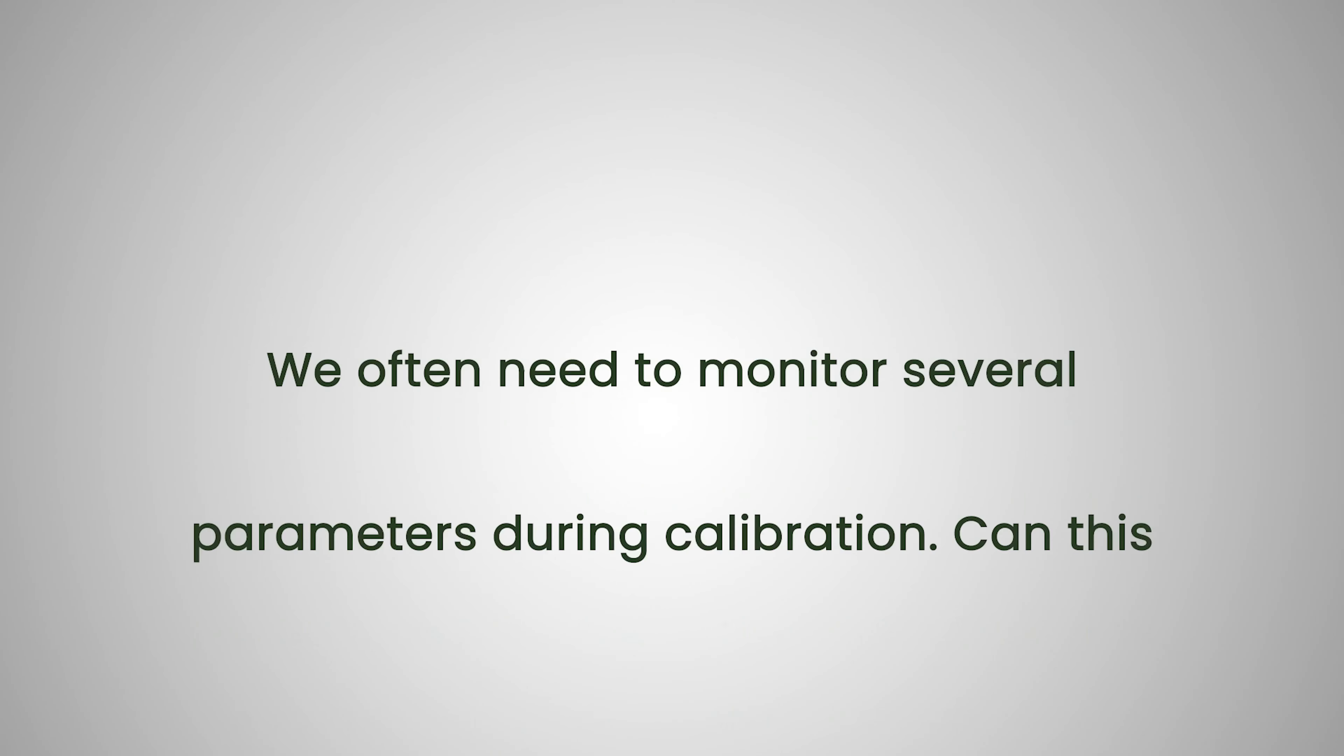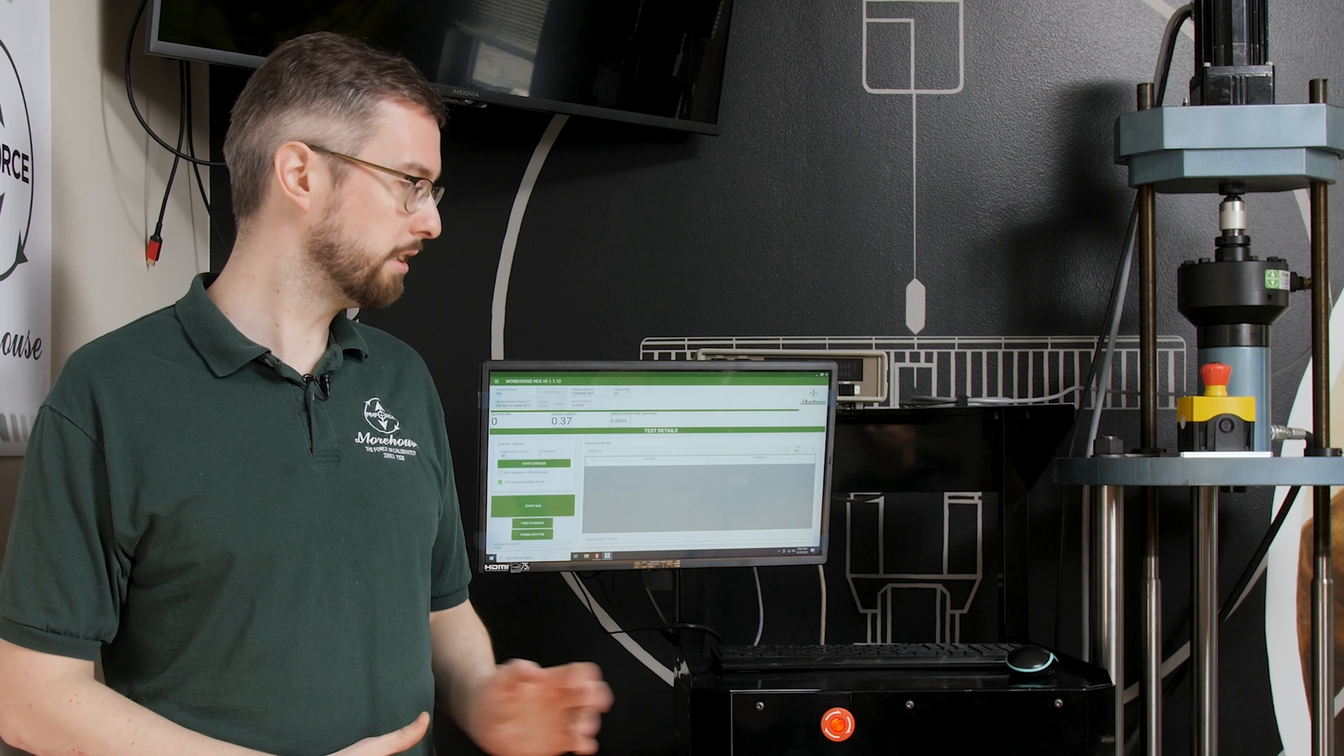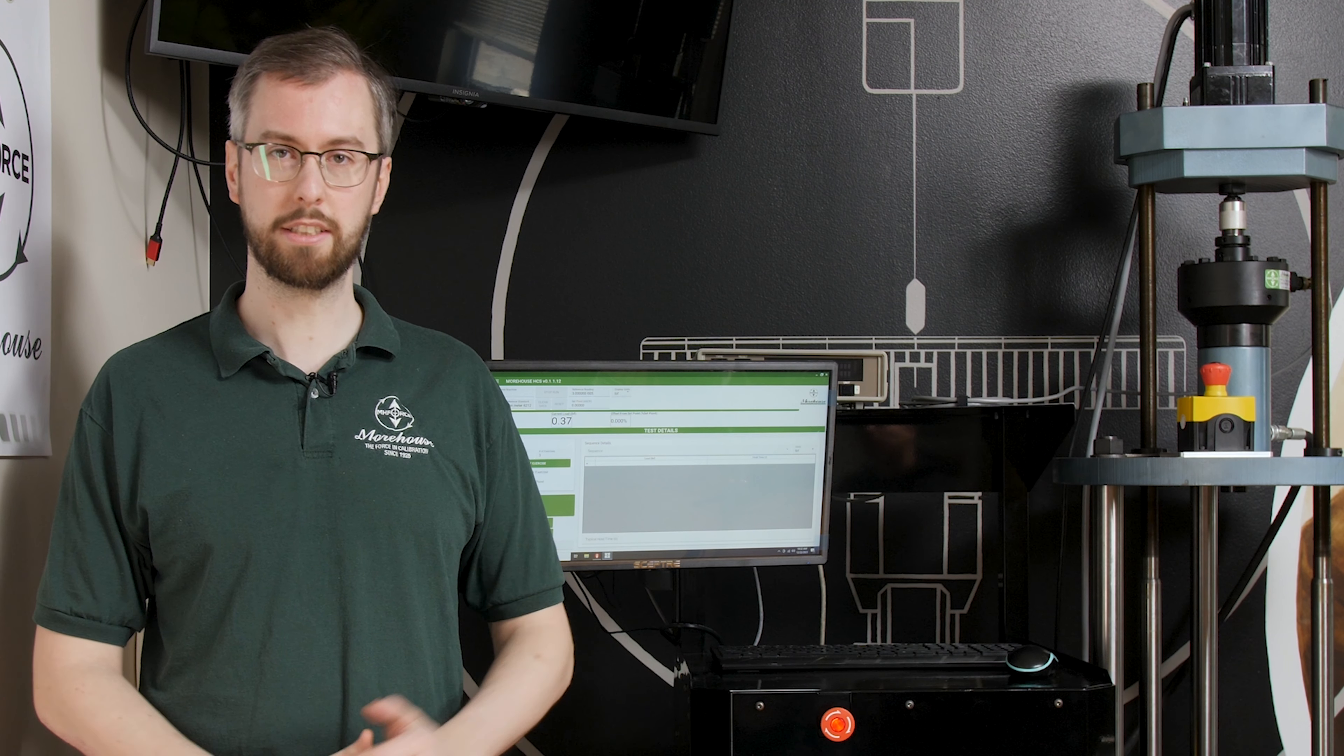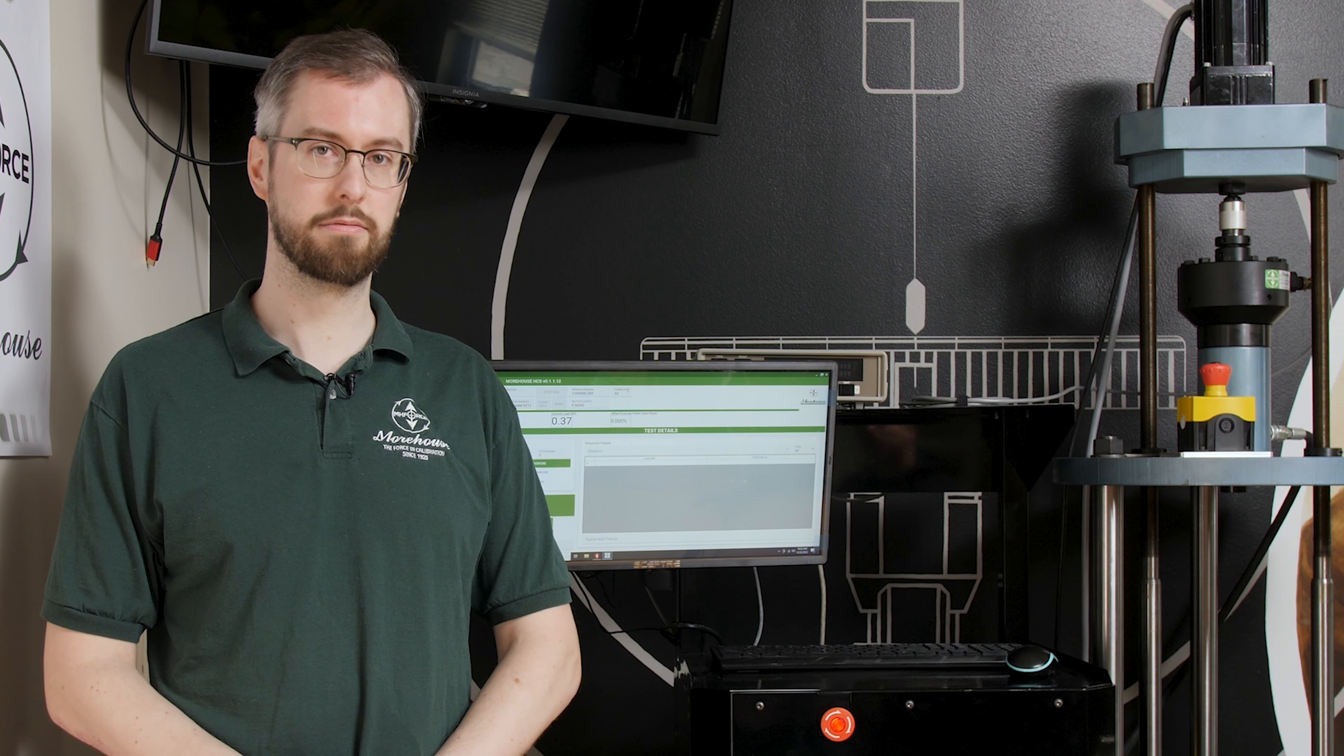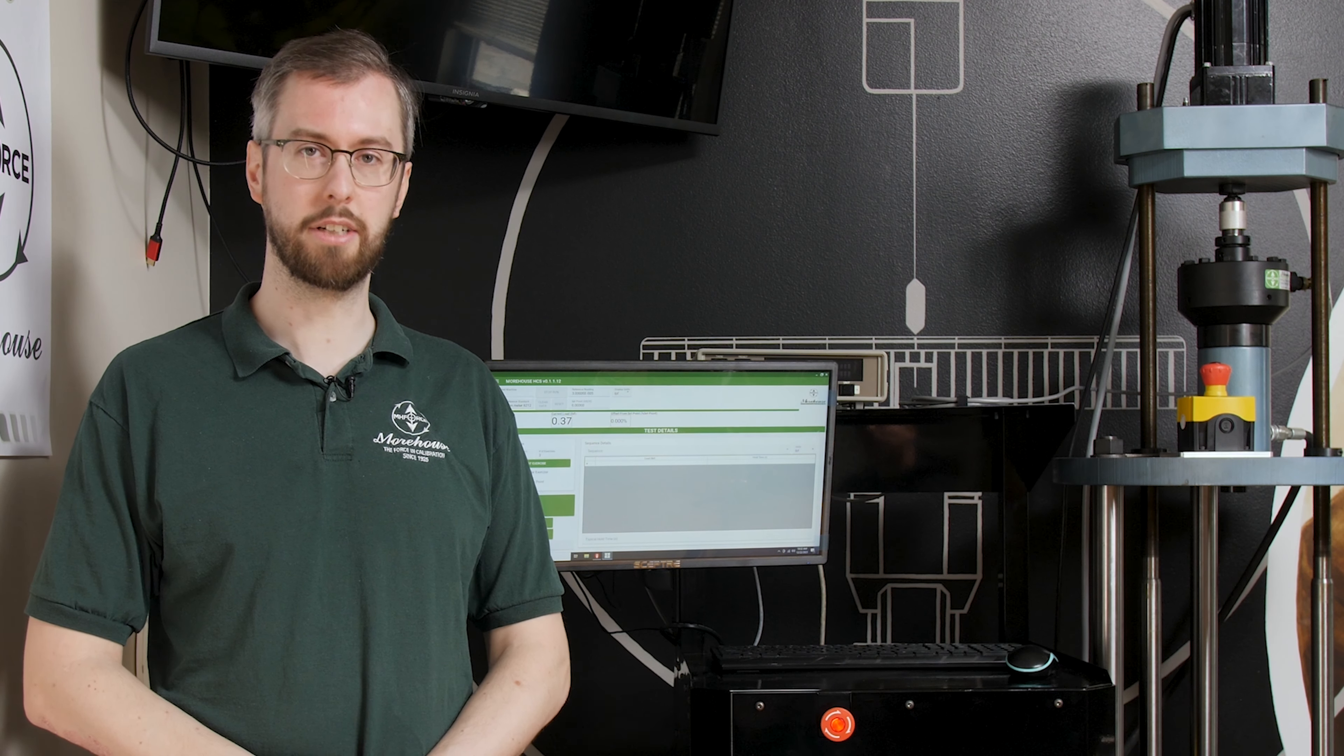We often need to monitor several parameters during calibration. Can this seamlessly collect data from various indicators simultaneously? This system can connect to as many devices under test as you'd like and capture all the readings simultaneously.